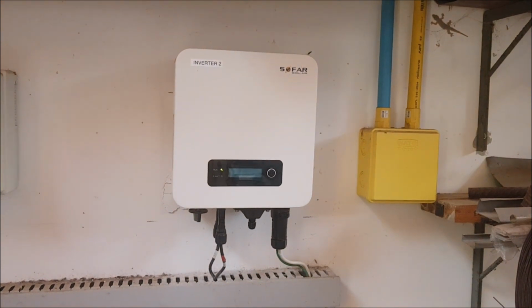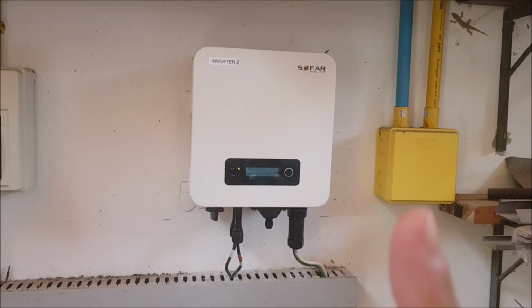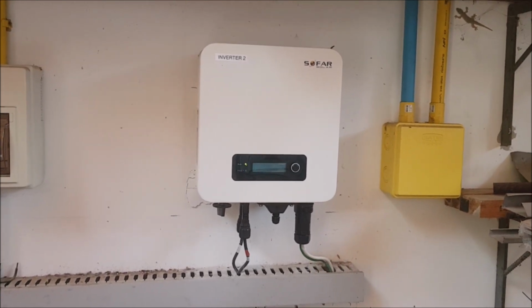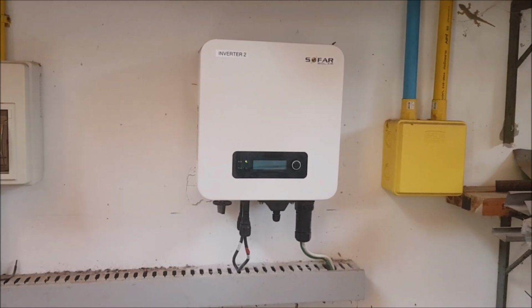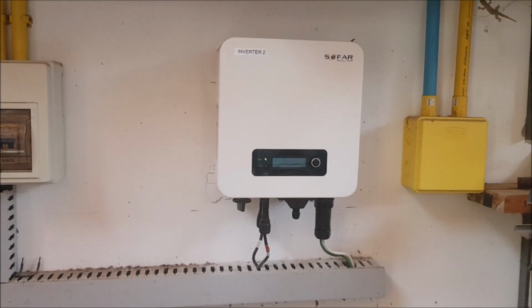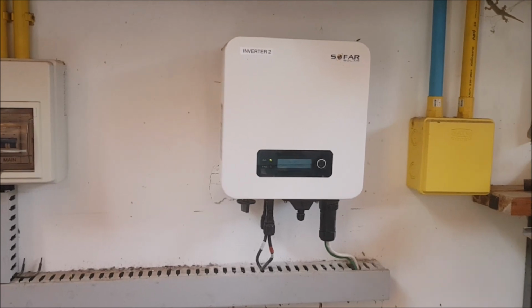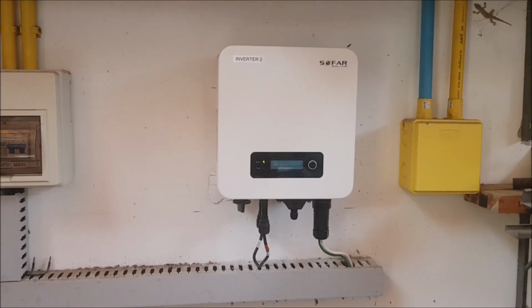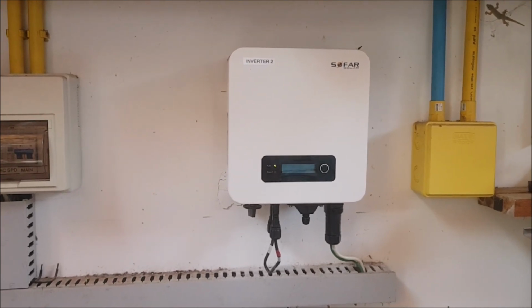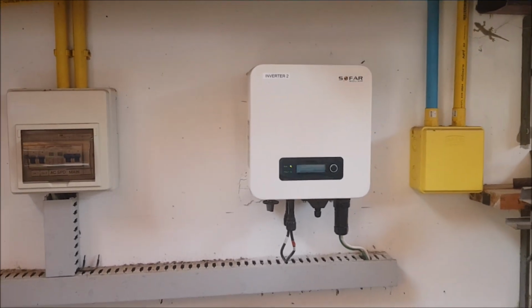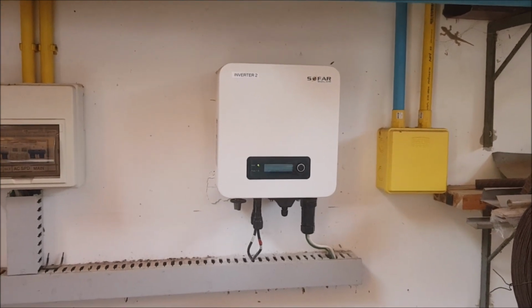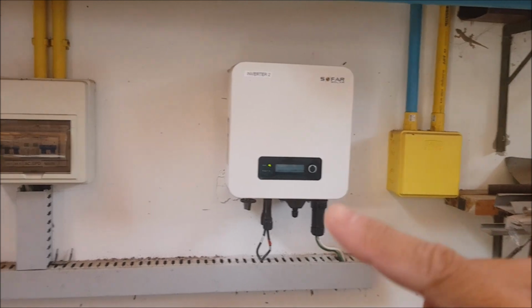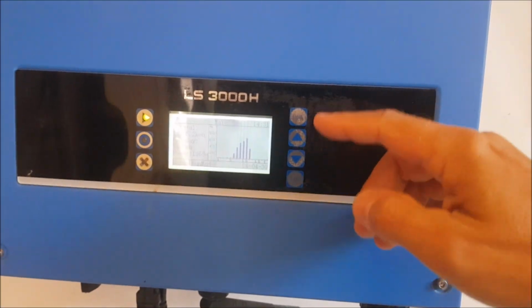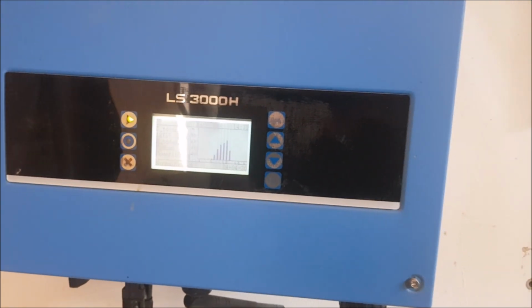Before, here was one of the blue ones, a 3000 watt, 2 MPPT inverter. The inverter that was hanging here actually went behind the coffee shop now, because there was an identical inverter which made some troubles. The trouble was that sometime in late morning around 10 o'clock it would kick out, showing a grid error, and then in the late afternoon around 3 o'clock it would come back on again. The problem was also that the buttons on the screen were not responsive anymore, so I could not go through the displays and menus to see what was actually going on with that inverter.